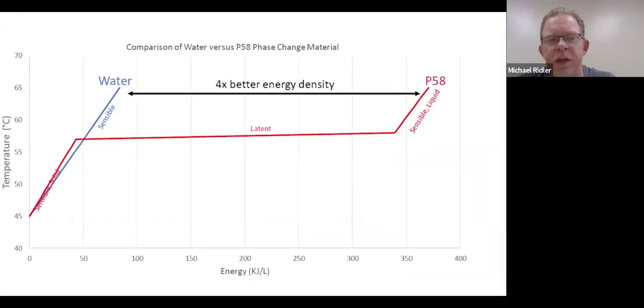If you look at this, the blue line on the left represents water. When I charge a water heater like the one you just saw, I'm storing sensible energy. I start at a low temperature and heat the water up very hot, because it needs to be at a condition where it won't form any bacteria. Then the tank itself will be hot at the top, usable heat, not as hot in the middle, and the bottom won't be usable heat. What's really unique about a phase change battery is that's not how it works.